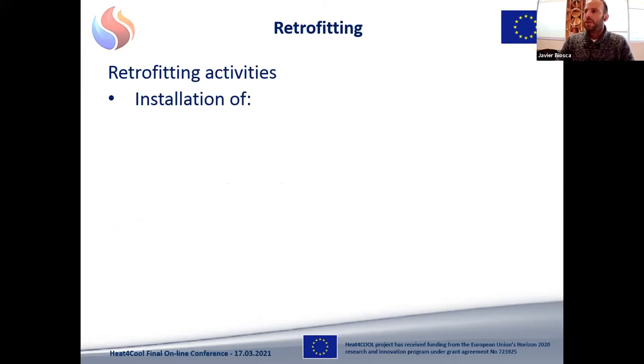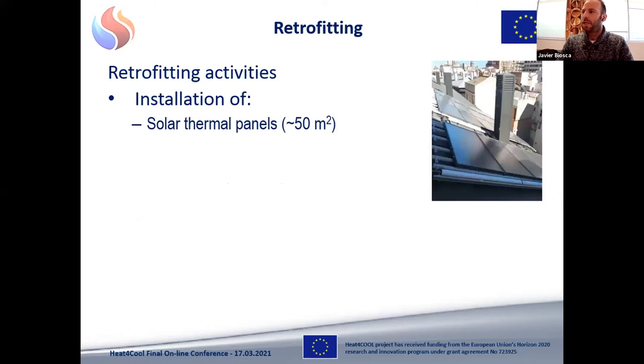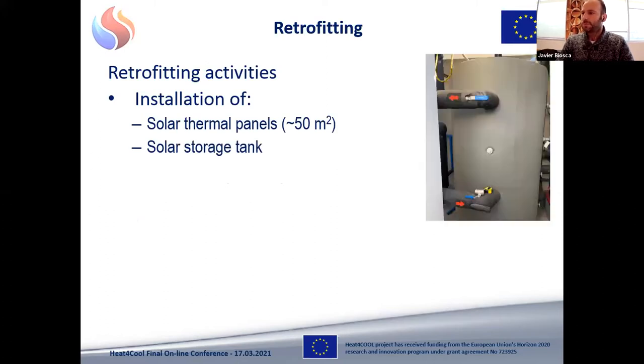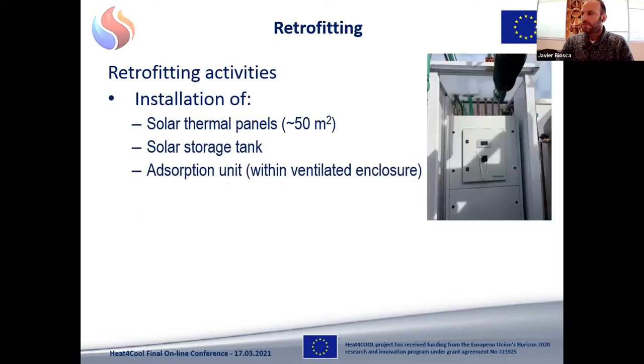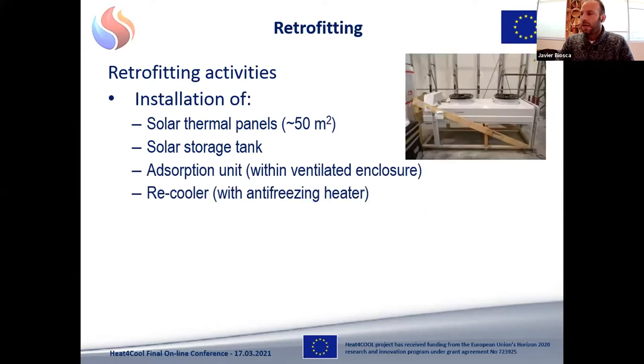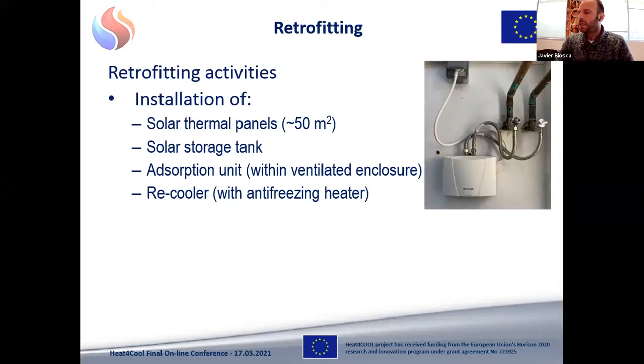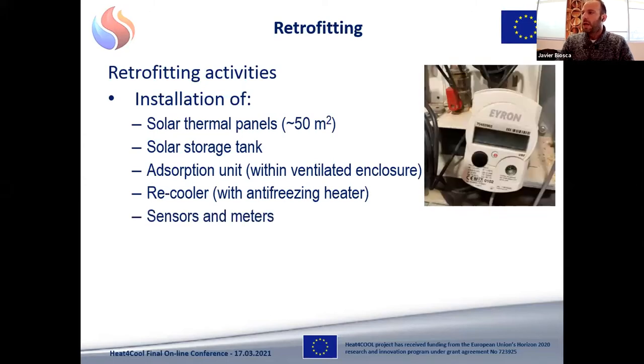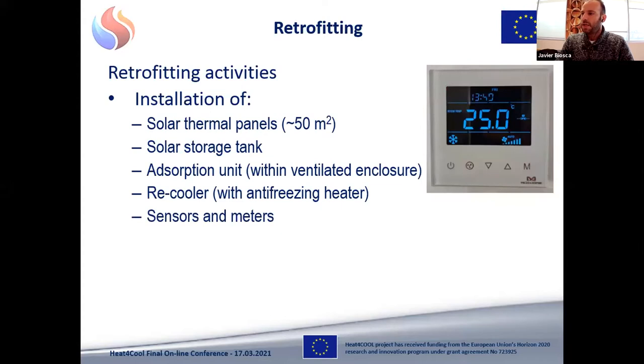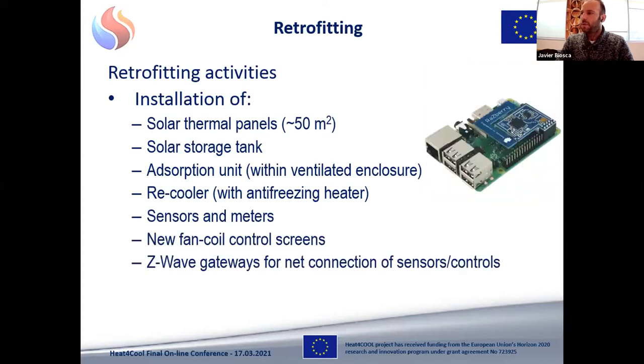Then the retrofitting activities were the installation of the solar thermal panels with around 50 square meters, the installation of the solar storage tank in order to store the solar production, and the adsorption unit within a ventilated enclosure, and the recooler with also an anti-freezing heater in order to avoid the freezing problems of the water contained inside, since this component is placed outdoors. Also, the installation of sensors and meters, new fan coil control screens, and Z-Wave gateways for the net connection of the sensors and controls. And the old gas boiler was also removed.